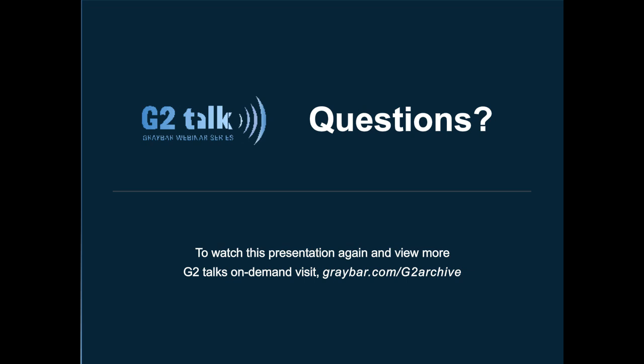Thank you, Suji. How about, how much larger is the OD of a VFD cable versus non-VFD cables? Ooh, that's a good question. VFD cables have a lot going on, so yes, they tend to be less flexible and larger in diameter. Definitely, if you look at them, they look like batons. They're very, very solid, and they're there for a purpose. So you have to design that into your system.